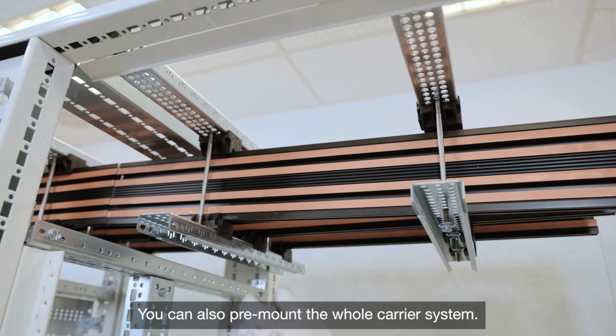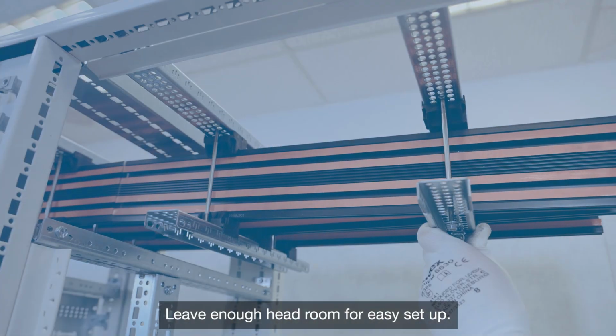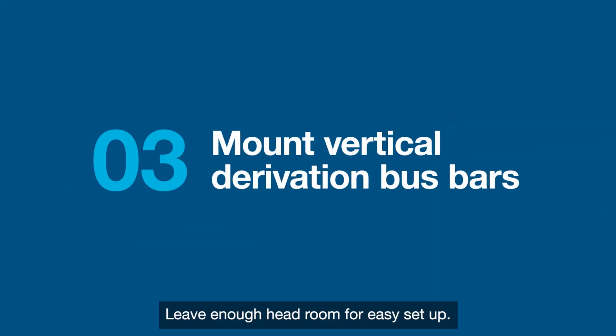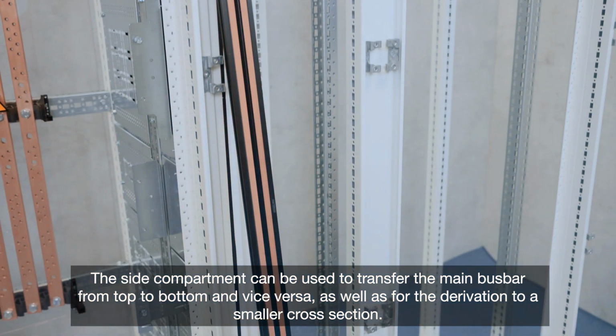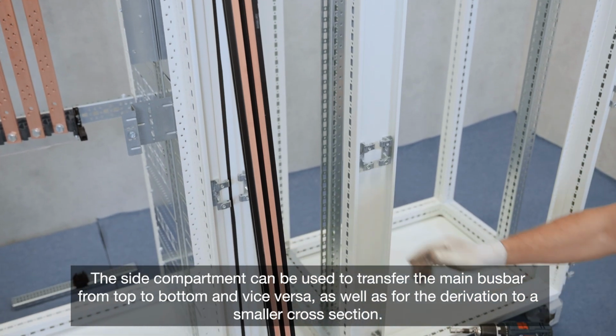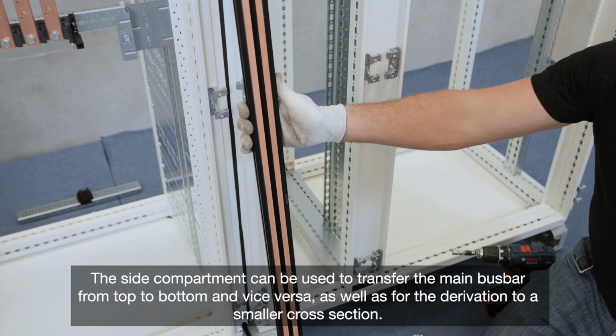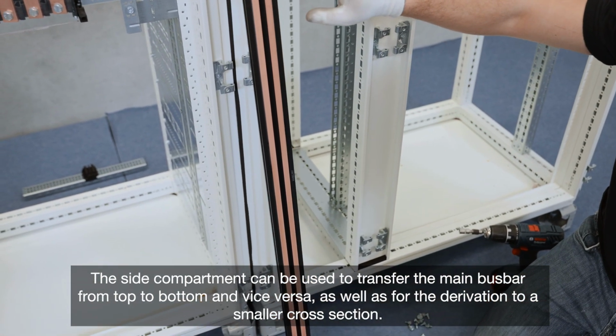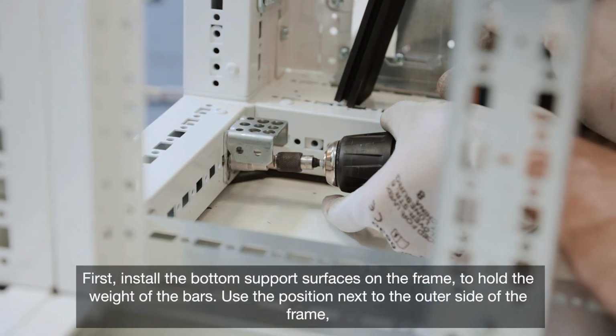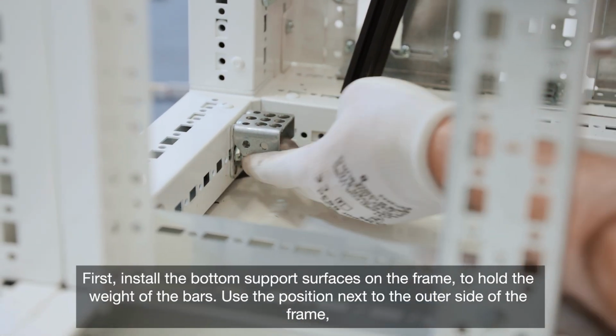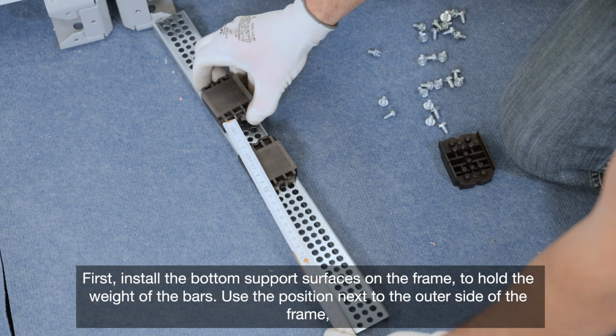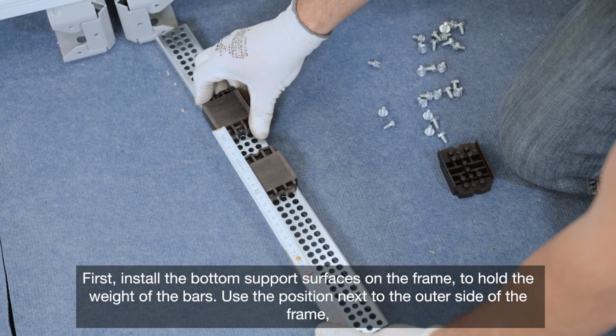You can also pre-mount the whole carrier system. Leave enough headroom for easy setup. The side compartment can be used to transfer the main busbar from top to bottom and vice versa, as well as for the derivation to a smaller cross-section. First, install the bottom support surfaces on the frame. To hold the weight of the bars, use the position next to the outer side of the frame.